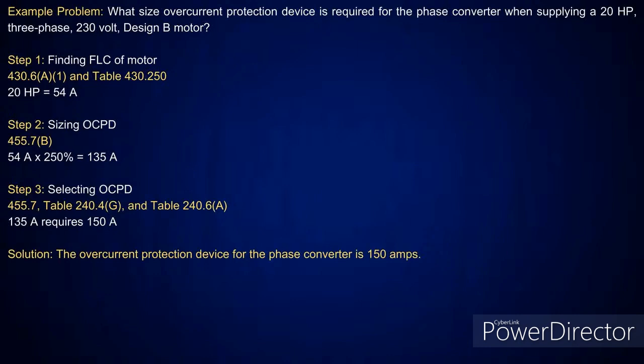Now, what you're going to get into, you're going to go over and you're going to look at 455.7B because we're dealing with phase conversion here. And when you go pick up 455.7B, this is where we're going to be. Now, if I was doing a variable load, would be different. And then I've got one that I'm doing a fixed load. This is a fixed load here. Okay. And when you're sizing your overcurrent protection devices here, you have to look at this, and it's going to tell you to take that at 250%, and that'll give you 135 amps, but it's going to tell you you have to protect the conductor. So the next size overcurrent protection device above that for table 240.6A is 150 amp.